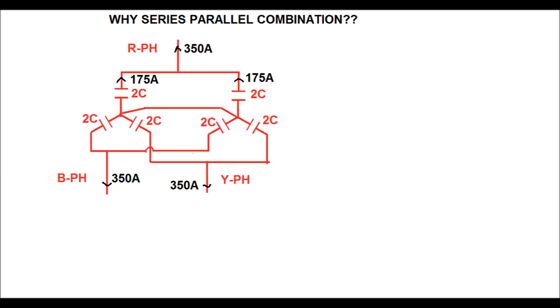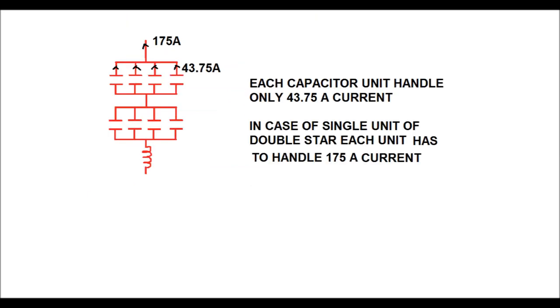In each star connection the current supplied per phase is 175 ampere. With the series-parallel combination, each capacitor unit handles only 43.75 ampere, instead of 175 ampere. If a single unit were used, it would have to handle 175 ampere — four times more current — making its design more complicated.